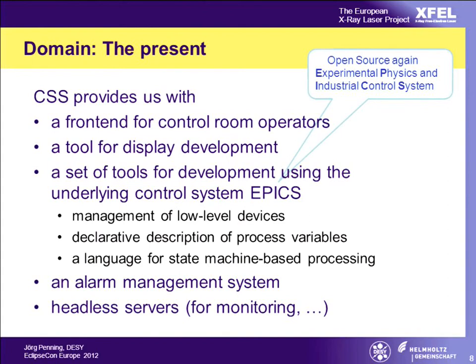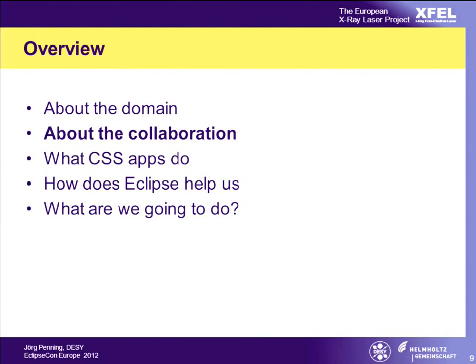We have a tool for display development, which is the main part of it. We have tools for development of the underlying control system - which happens to be EPICS at our place. We can manage low-level devices, use a declarative style of generating databases describing the system, and we have a state machine language integrated into EPICS which we can edit and compile. We have an alarm management system - the most crucial part, since usually the operator just waits for something to happen. We also have headless services for monitoring.